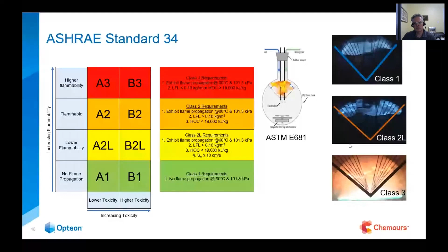The next thing, I'm going to quickly run through a couple of charts. This is 454B, an A2L, in this column. This is propane, an A3, in this column. We're going to run through several different tests that they do on flammability. The first one is lower flammable limit. This is how many grams of refrigerant would leak into a space, in this case a cubic meter. You can kind of envision a cubic meter. How much would you need to form a combustible mixture? You can see that with propane, you need a very small amount, whereas with an A2L, in this case 454B, you need a much larger amount to form a combustible mixture. So this is good. This is what you want, something where a larger leak would need to occur to get into a combustible mixture.